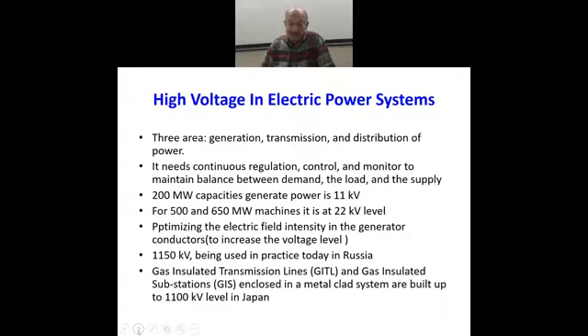And then from 22 kV at the generating stations, the voltage at which it is being generated, maybe 11 kV or 22 kV, is enhanced. It is stepped up for transmission purpose, because for transmission at 22 kV, it is not advisable. We'll see how. It may have a lot of losses because the current will be high, etc. So for transmission, we need higher voltages.